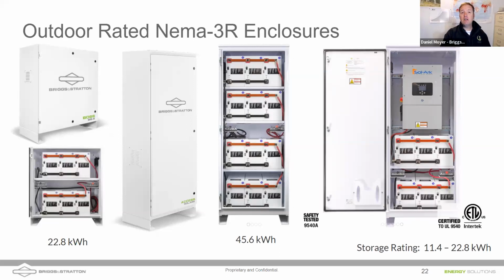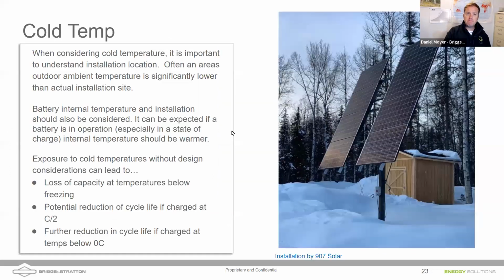We'll talk in a second about ways to insulate this cabinet. Think about Sol-Ark sitting at the top of the cabinet, that's generating heat. So not only can batteries generate heat, but other balance-of-system parts inside an enclosure can generate heat too, keeping the batteries a bit warmer. You're seeing some of our bus bars here, and also terminal blocks.